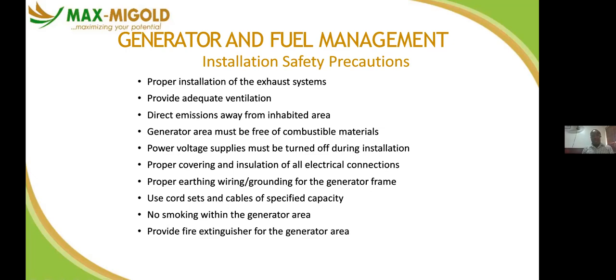Power voltage supply must be turned off during installation. Proper covering and installation of all electrical connections. You must ensure that all cables and all electrical connections are well insulated and protected. Earthing is key. Proper earthing and grounding for the generator frame. So use cord set and cable of specified capacity, and don't allow anybody to smoke around your generator. What you do is put a no smoking sign, a safety sign, do not smoke here, or danger, unauthorized persons prevented. So you put all that into consideration.